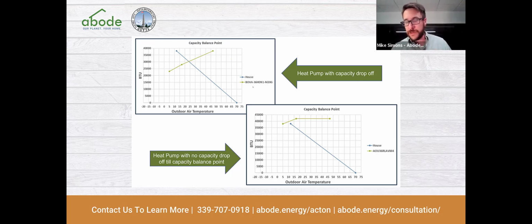But if we look at the bottom right-hand side, instead of a unit that does have a capacity drop off, we're looking at one that doesn't. This one is from Fujitsu. We would see that this house, down to the design temperature, which was 12 degrees, needs 36,000 BTUs. This 36,000 BTU unit actually always has more capacity than the house is going to require at its design temperature. So it does fall off a little bit once we get down to the single digits, but it can still be sized so that it's always greater than the heating design load.